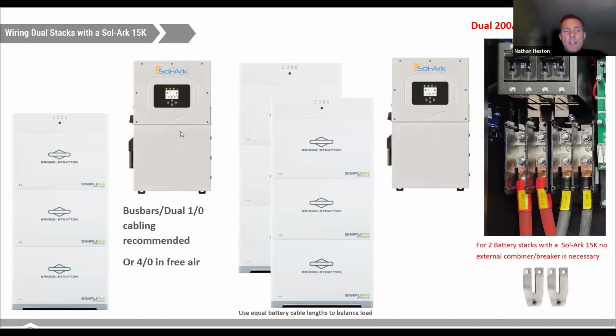If you are doing a single stack of batteries, we still recommend running dual cabling, bringing one set of cables to each of the inputs on the Sol-Ark. That makes pulling the cable easier. It's easier to work with dual 1-aught or dual 2-aught cables. As well, each of your individual cables would then be protected with the individual breakers there. So if you use dual 2-aught, which is my preference, then your cables are protected.